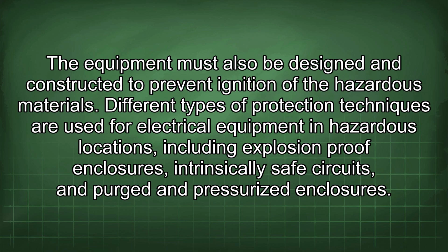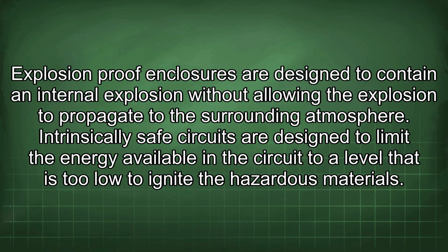Explosion-proof enclosures are designed to contain an internal explosion without allowing the explosion to propagate to the surrounding atmosphere. Intrinsically safe circuits are designed to limit the energy available in the circuit to a level that is too low to ignite the hazardous materials.